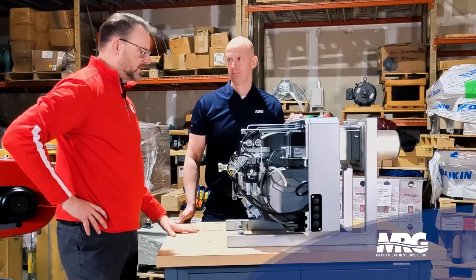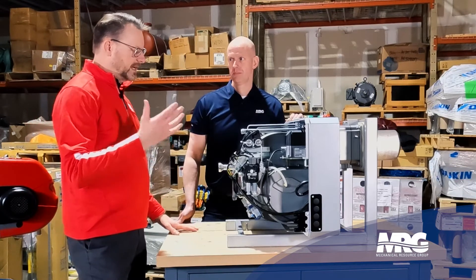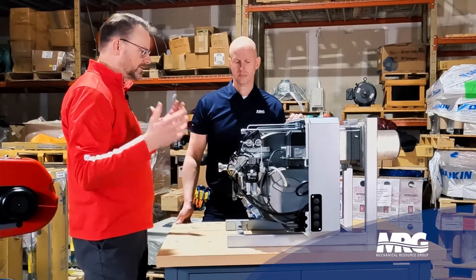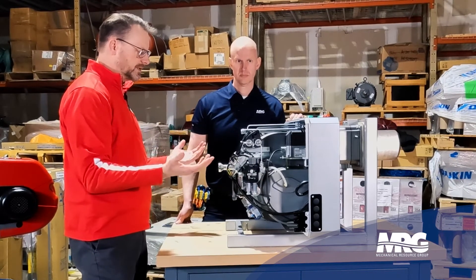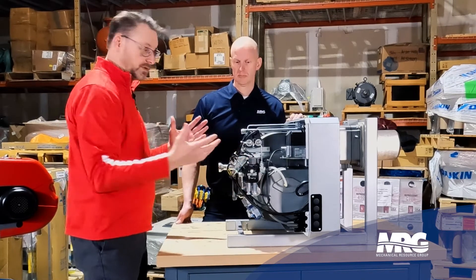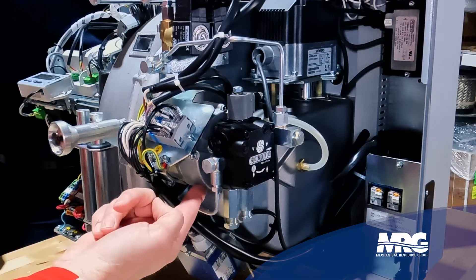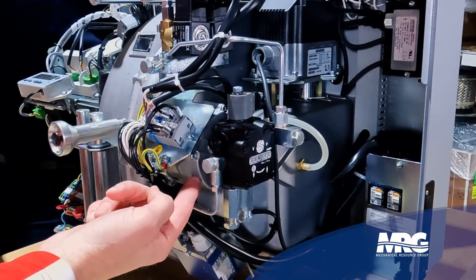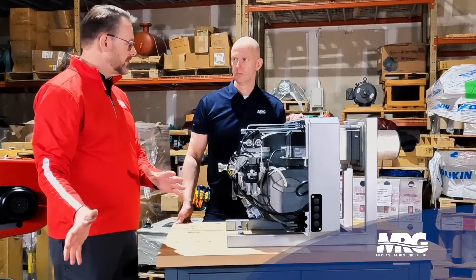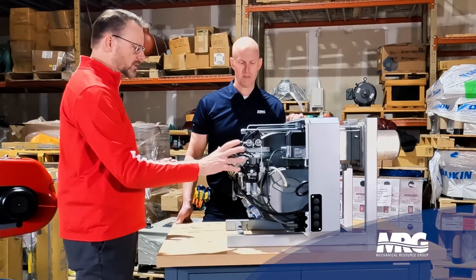Specifically for resilient applications where it is desired to have an alternate fuel, the Riello philosophy has been to provide a distinctly motor-driven oil pump on the unit. So this unit comes for gas-oil. You connect the gas to it as anyone would. Something unique we do is provide a distinctly motor-driven oil pump here to supply oil flow to the nozzles and give you that oil firing. It is not driven by the blower motor, and it is not set someplace else needing to be piped, wired, and controlled to synchronize with the burner.